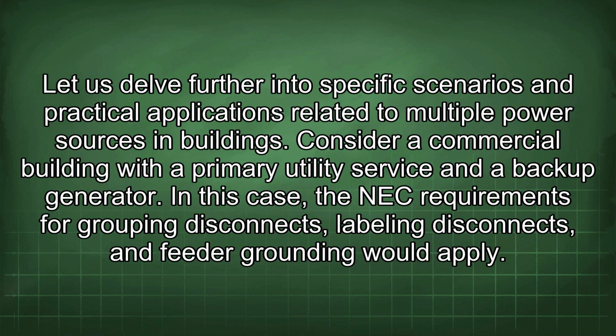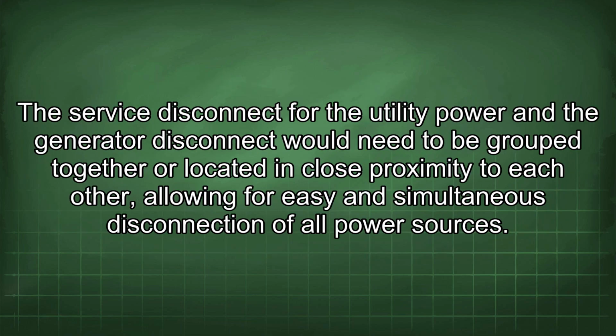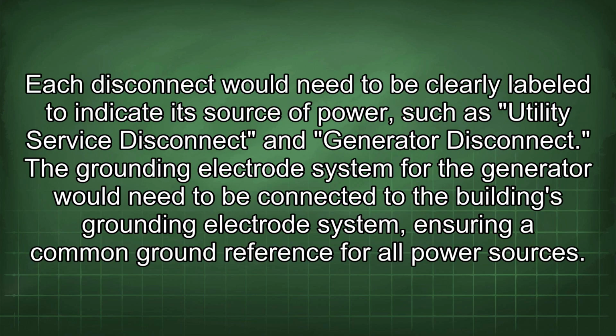Let us delve further into specific scenarios and practical applications related to multiple power sources in buildings. Consider a commercial building with a primary utility service and a backup generator. In this case, the NEC requirements for grouping disconnects, labeling disconnects, and feeder grounding would apply. The service disconnect for the utility power and the generator disconnect would need to be grouped together or located in close proximity to each other, allowing for easy and simultaneous disconnection of all power sources. Each disconnect would need to be clearly labeled to indicate its source of power, such as utility service disconnect and generator disconnect. The grounding electrode system for the generator would need to be connected to the building's grounding electrode system, ensuring a common ground reference for all power sources.